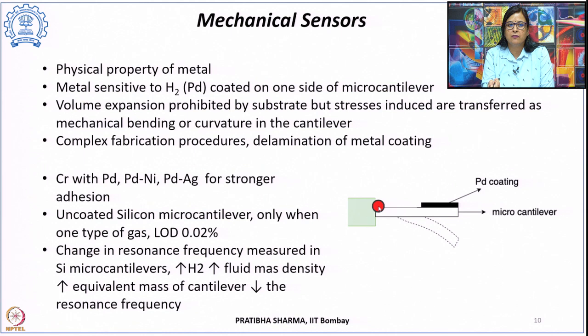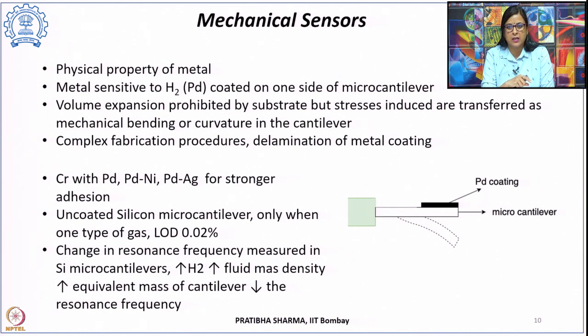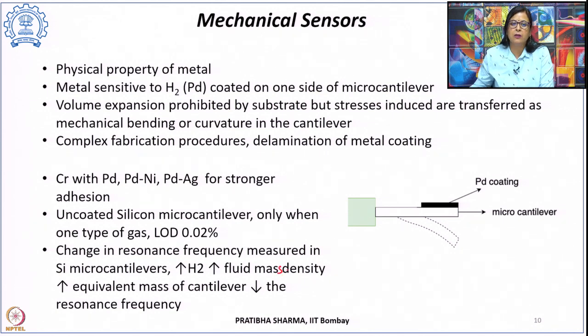To improve adhesion, chromium-palladium, palladium-nickel, or palladium-silver alloys can be used. Alternatively, an uncoated silicon micro cantilever can be used, with a limit of detection of about 0.02%, based on changes in resonance frequency. As hydrogen gas concentration increases, fluid mass density increases, raising the equivalent mass of the cantilever and decreasing the resonance frequency, which is then calibrated to hydrogen concentration.